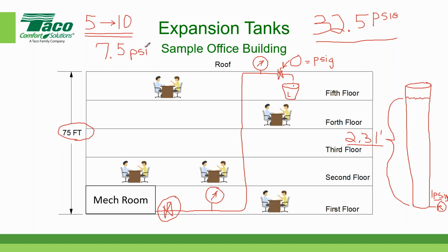I want pressure at the top of the system for multiple reasons. First of all, I want enough pressure to push the air out. If I have some air vents at the top, and if there's any air trapped at the top of the piping system, I want enough pressure to push the air out. I want enough pressure to prevent cavitation, either through a pump or some other device connected to the system. And I want enough pressure so that my piping system is not airbound in any way.